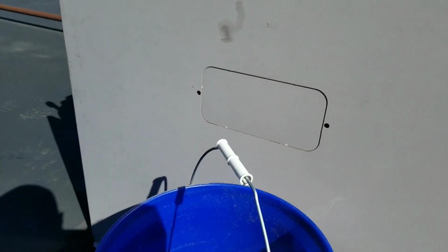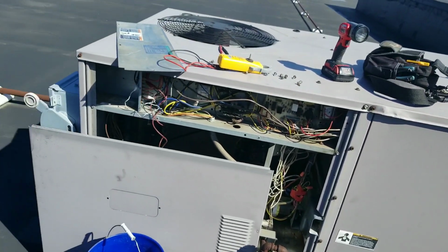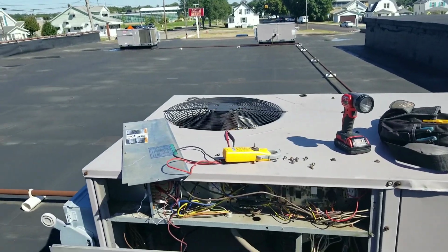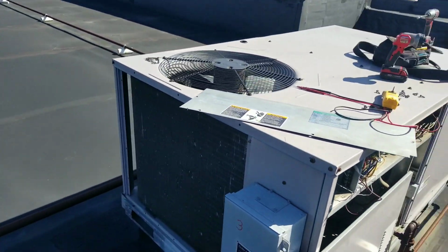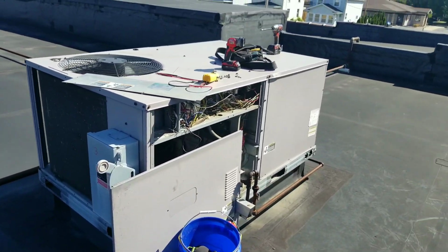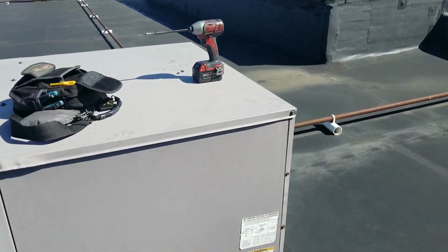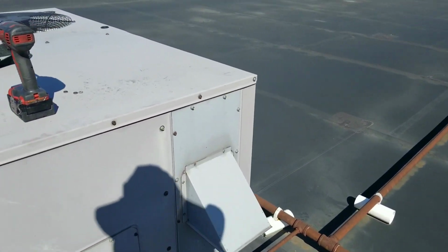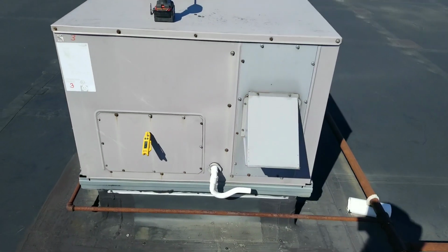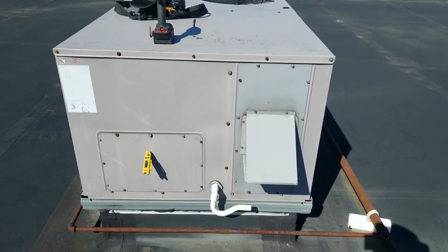Let's get over here. See if we can grab some lines. See, our discharge line back there is warm. Not as warm as I was thinking it would be, but it's probably about 65, maybe 70 degrees out today. Nice and cool in the store, so probably not getting a whole lot of a load. I'm going to check my return air temperature here in a minute. Alright guys, let's let this run for a little bit. See what happens, alright?